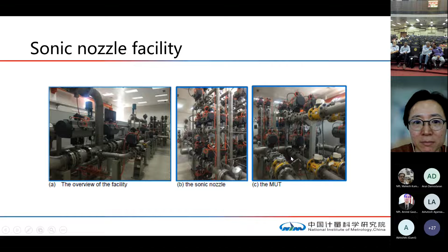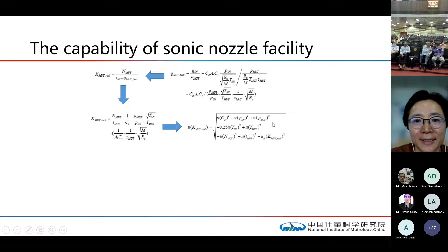And there's additional pipelines for the customers, the customers flow meter. The principle for the sonic nozzle is like this. Finally, the uncertainty can be expressed like this. The biggest challenge for the sonic nozzle facility is, you can see here, the pressure range for our sonic nozzle facility is from 100 kPa to 2500 kPa.